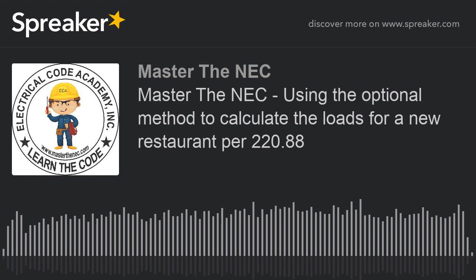But you have all the rules in 310.14 that you have to meet as well, which is adjustment and corrections and everything else. But remember that this is where we get the infamous 240.4(B), whereas if it's 800 amps or less, the next standard overcurrent device rating shall be permitted to be used. Again, this is where you would have, let's say, a conductor that's rated for 37 amps that could be protected by a 40 amp breaker, and it would be okay.